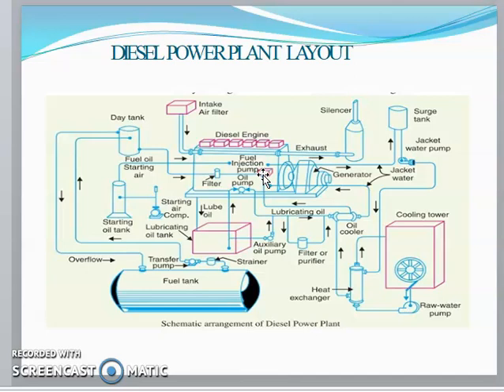Diesel engine power plants are mainly installed where the supply of coal and water is not available in sufficient quantity, where power is to be generated in small quantities, or where standby sets are required for continuity of power supply — such as in hospitals, telephone exchanges, radio stations, and cinema theaters. Generally these plants range from 2 to 50 megawatt capacity and can also be used as central stations.